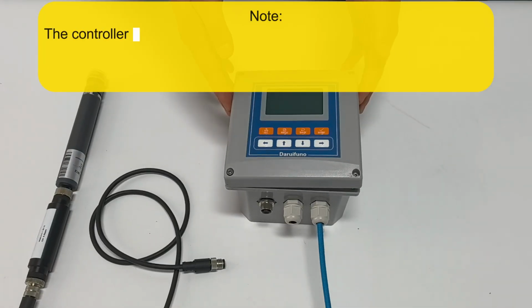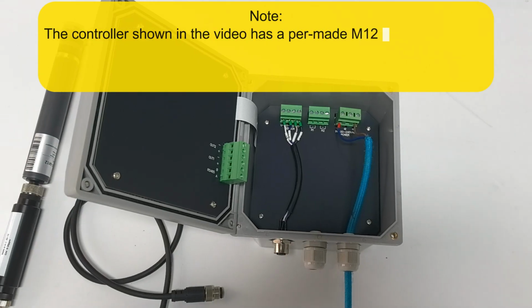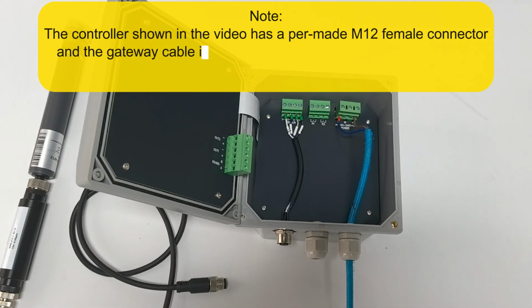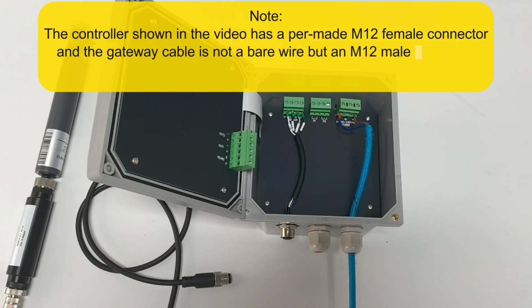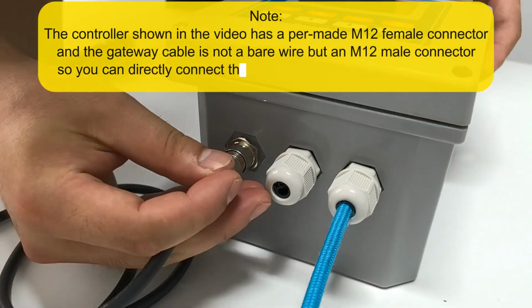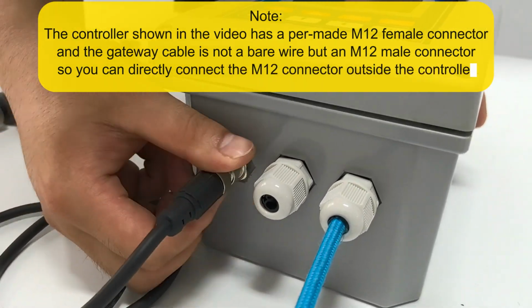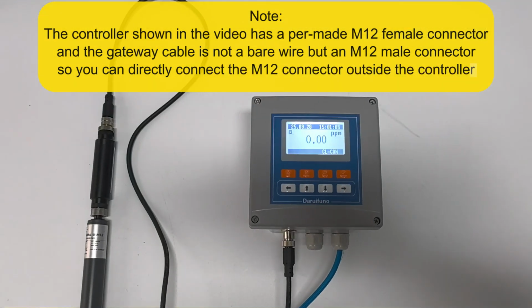Note: the controller shown in the video has a pre-made M12 female connector, and the gateway cable is not a bare wire, but an M12 male connector. So you can directly connect the M12 connector outside the controller.